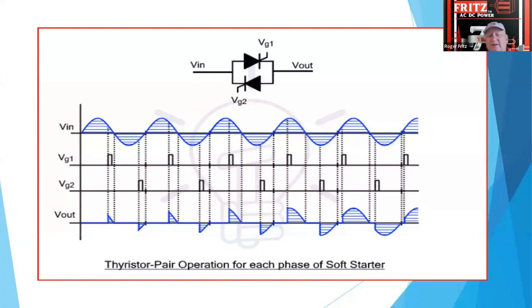So what it's literally doing, as here are the voltage waveforms coming from the power line, is slowly switching it on. It doesn't allow the SCR to pass until it gets to this point, and it's a very small amount of voltage. Then as it ramps up, you can see we can regulate how fast it's bringing that waveform to the motor. And so it ends up creating soft start.